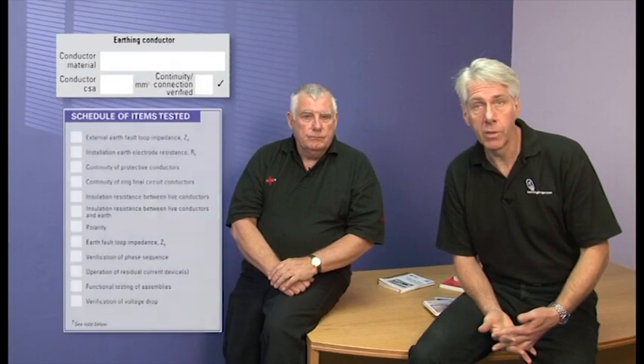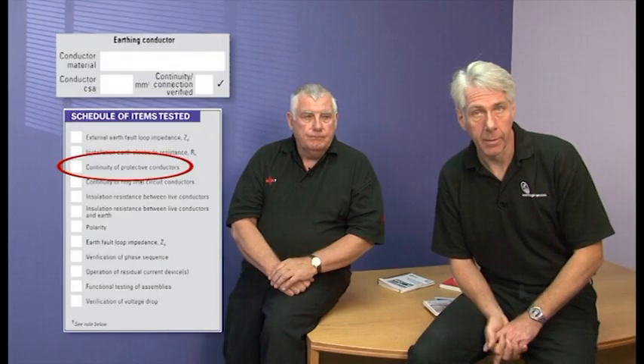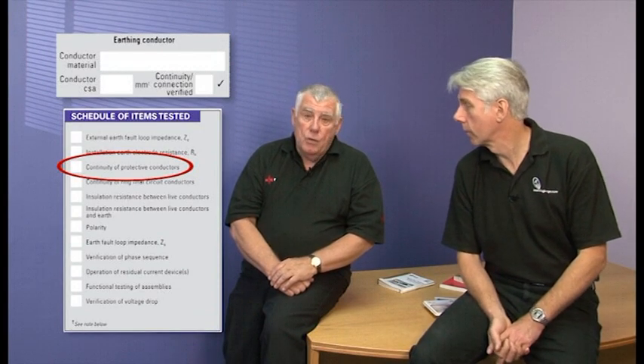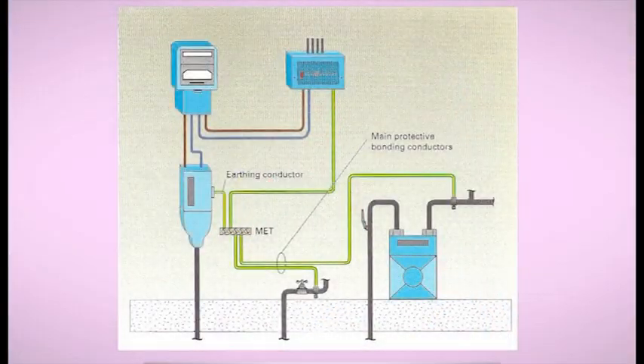Within the section concerned with protective conductors, there is a box to confirm that both the connection and continuity of the conductor has been verified. This could either be a visual means of checking continuity or confirmed by testing. Just to let you know that when we say visual check, we mean that you can see the entire length of the conductor. So even though it might only be for a couple of metres, if it passes through a wall at any time, you will have to confirm continuity by measurement.